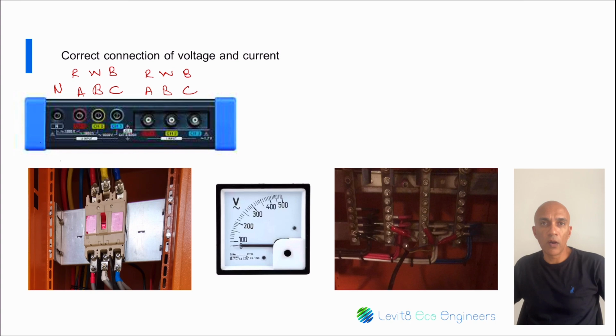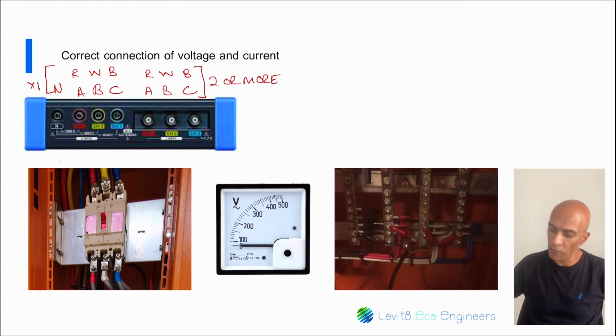So some instruments allow measurement of multiple feeders on a common bus, and in those cases, the common bus will have the same voltage. There is one set of voltage measurements and 2, 3, or 4 or more sets of current inputs. Note that each set would be three-phase. So if you're measuring on a common bus, you'd have one of these voltage, and you might have 2 to 4 of these. Or it could be more, it could be less, it could be 3. It depends on the type of instrument that you are using. But remember, it has to be on a common bus. Then only will all your power information be the same.